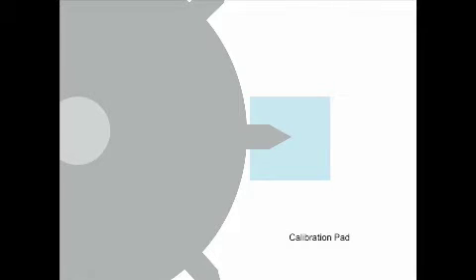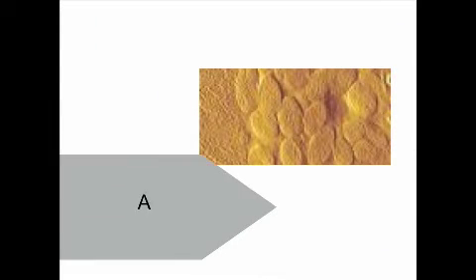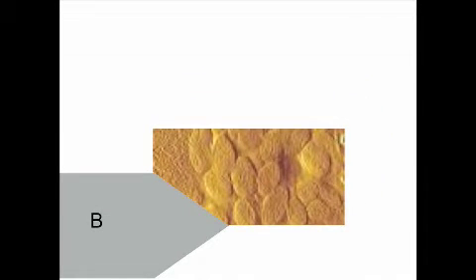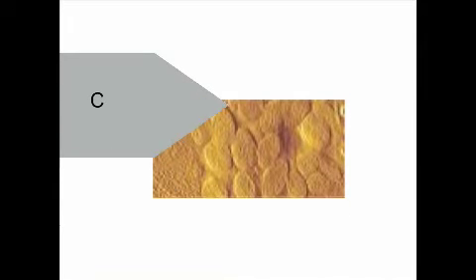Since all the cantilevers have to be manually loaded around the perimeter of the rotating head, a one-time computerized calibration procedure is required to be run in order to record all the tip offsets relative to the other tips. By using a calibration pad, which utilizes technology similar to a capacitive or resistive touchscreen found on tablet PCs, a computer system stores the position of the tips relative to all the other tips by simply touching each tip to the pad. With the position data stored in the computer now, during the real-time scan, the sample stage can then be repositioned using the distance information corresponding to each tip selected for use.